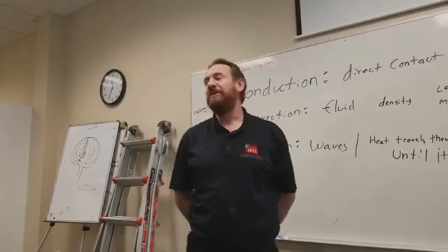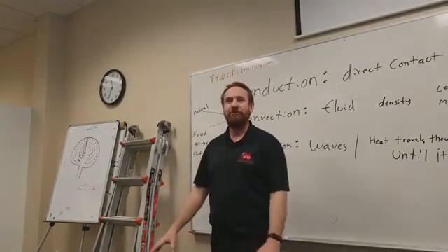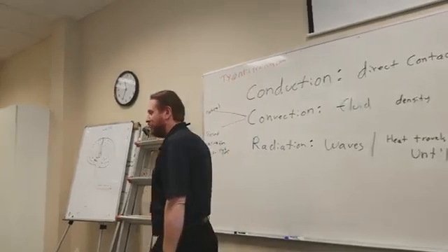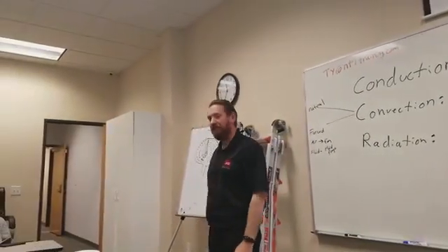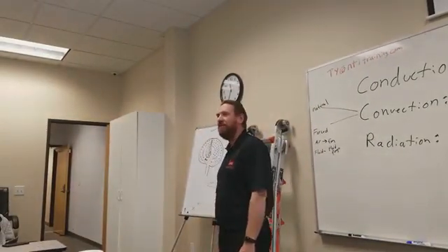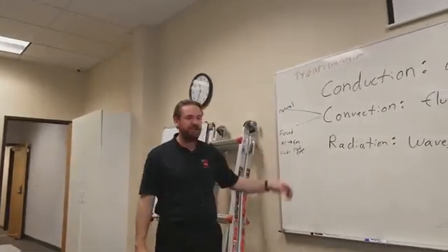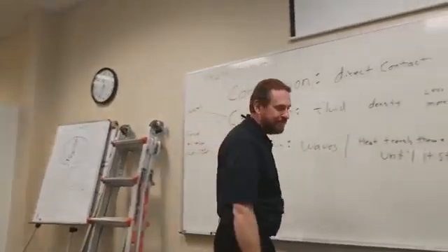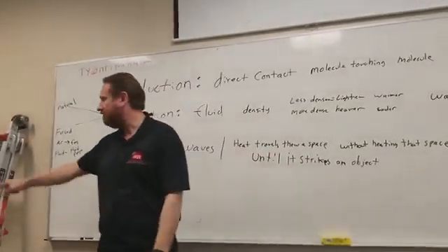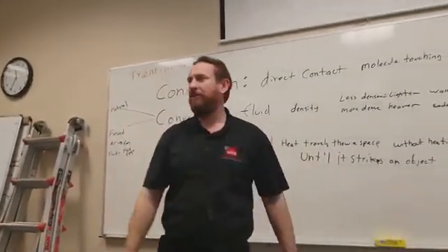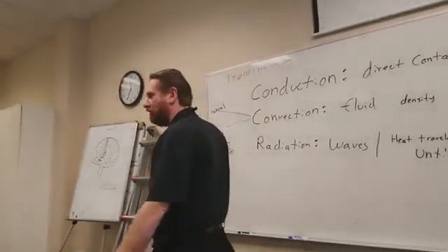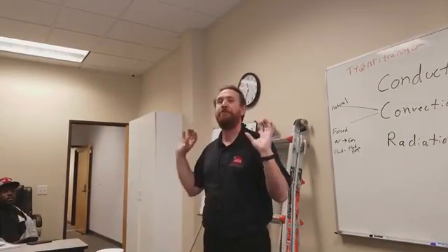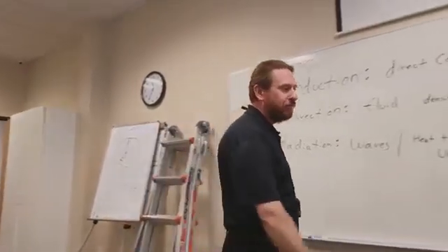So what they'll do is use heated floors. They call it radiant heating, but really it's not. What we do is take pipes. We have a water heater that heats water. We have circulating pumps. We have forced convection, and we force the movement of heat through a fluid. We run those pipes back and forth through the floor, and then we'll pour concrete over those pipes. Or sometimes we'll hook the pipes to the bottom of wood floors even. Either way, we take the fluid. It doesn't have to be water.